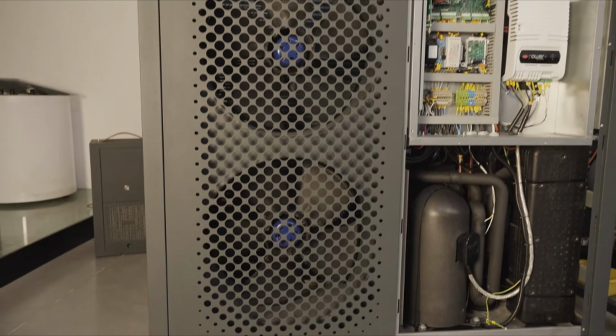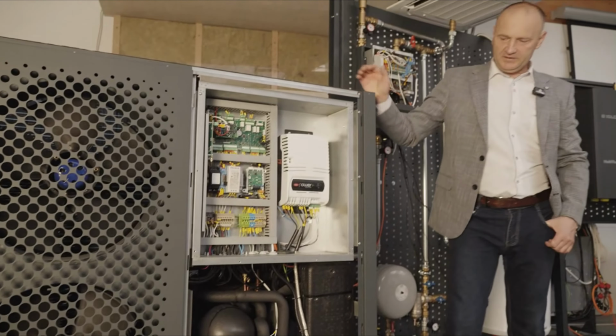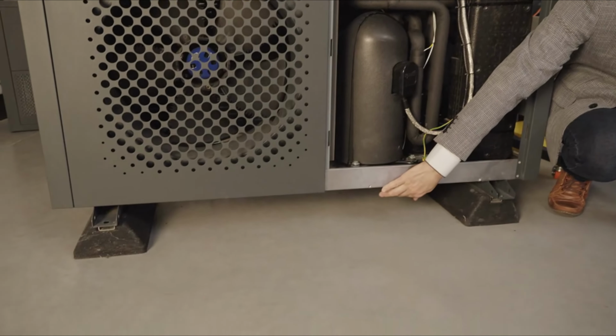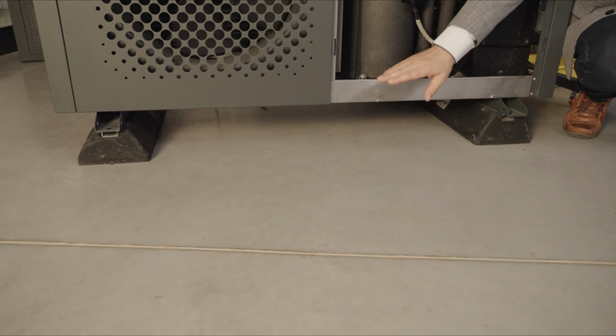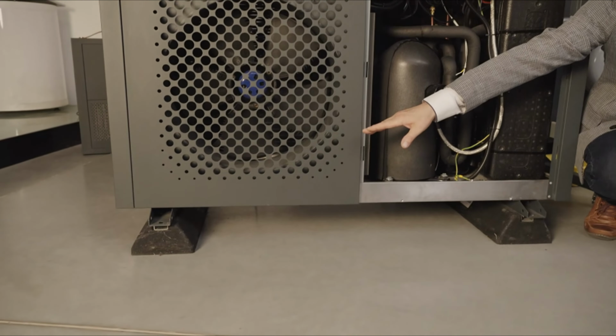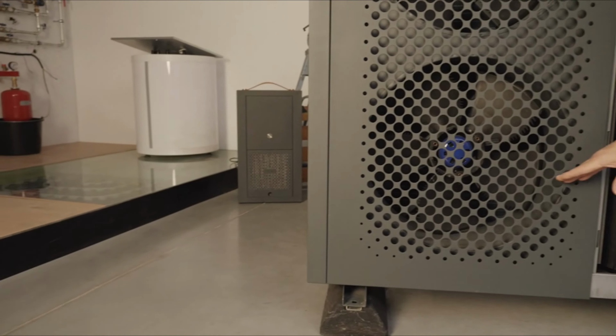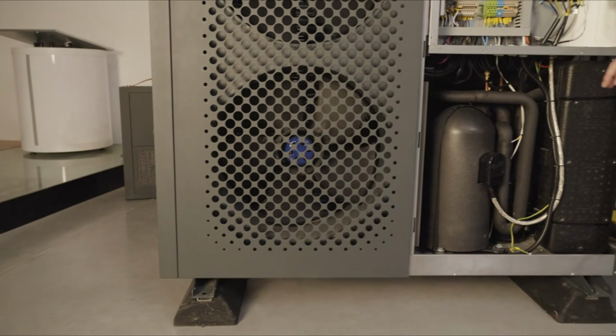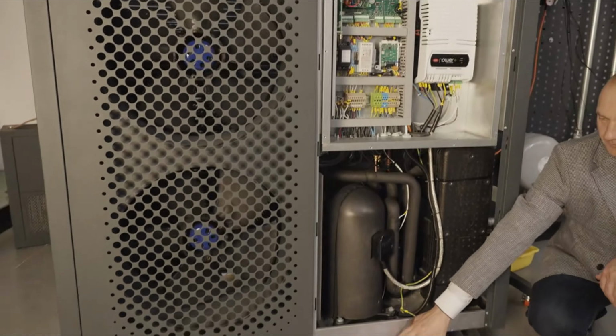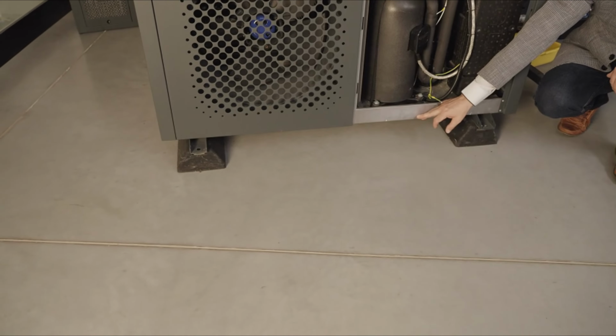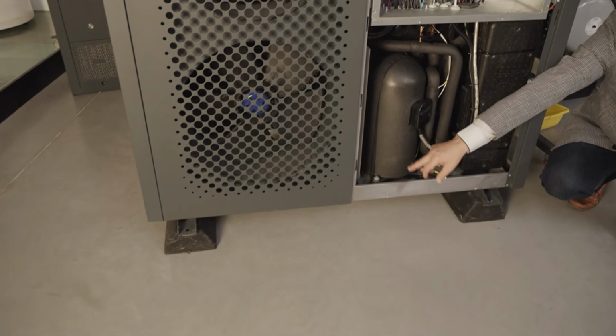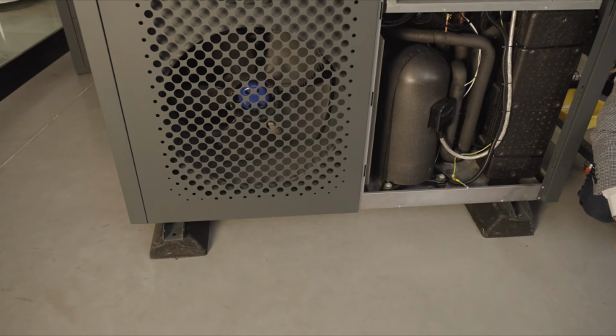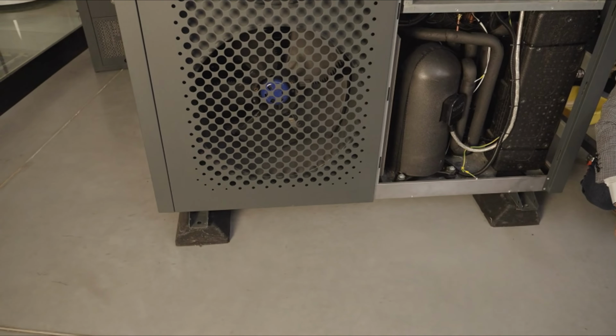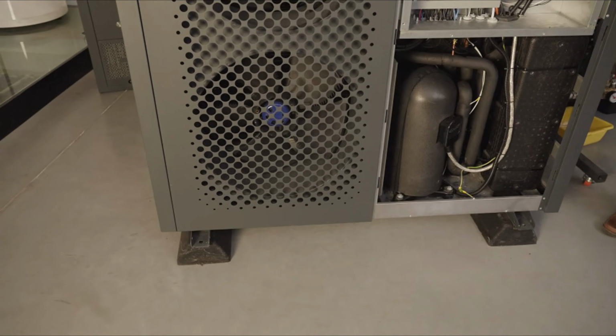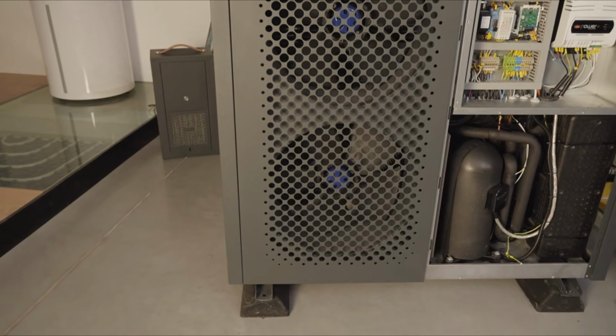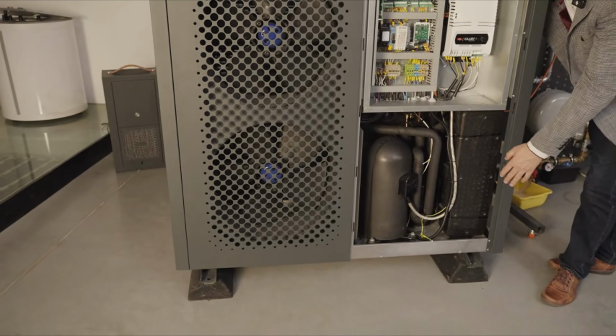This tray is designed to be heated specifically by the liquid refrigerant and is constructed in such a way that its bottom part is made of acid-resistant stainless steel sheet and the top part is made of ABS. This is an ABS molding. It's visible inside under the fan. It features a funnel for condensate drainage and, positioned between the ABS casing and the acid-resistant sheet metal, there is polyurethane foam and a copper coil, which actively heats the drip tray using a liquid refrigerant. This innovative design not only provides cost-free heating for the drip tray, but also ensures exceptional energy efficiency for the entire unit.